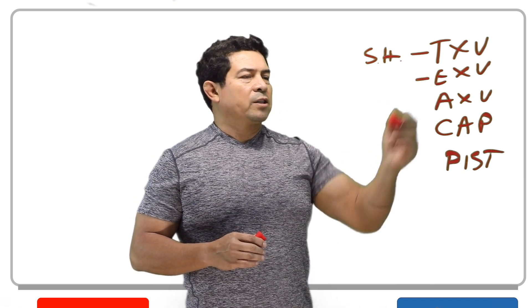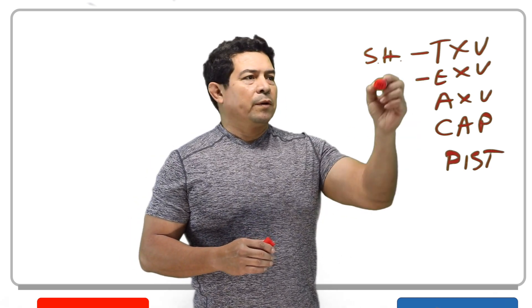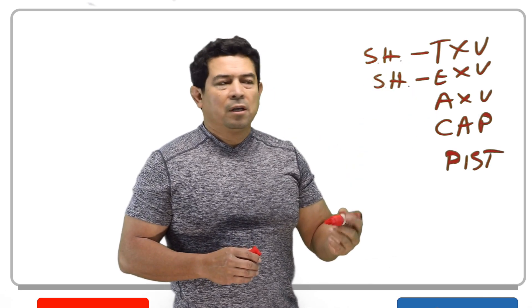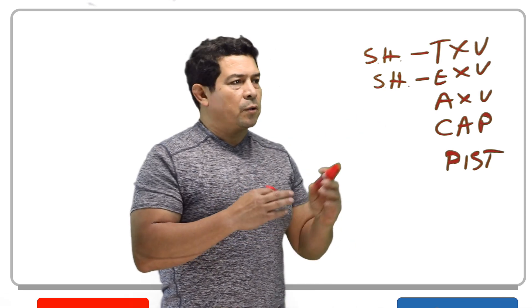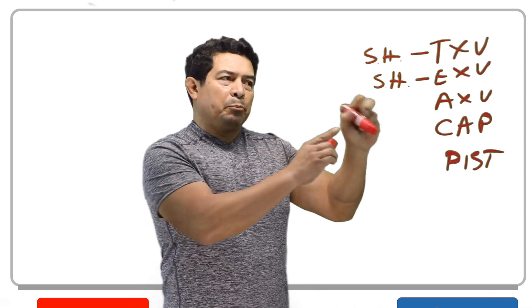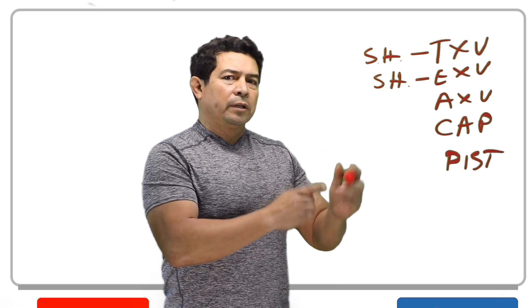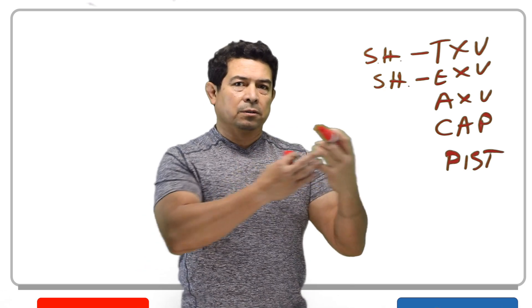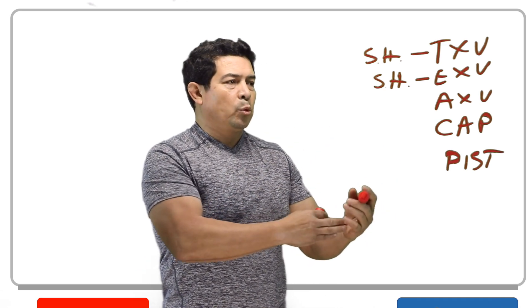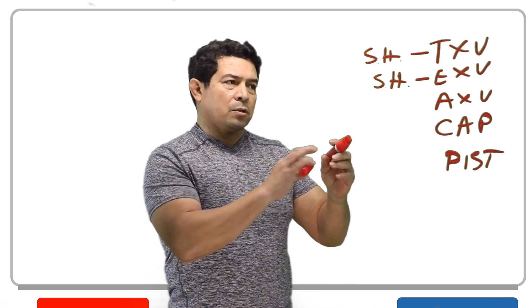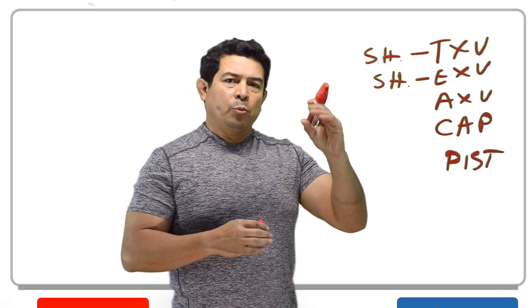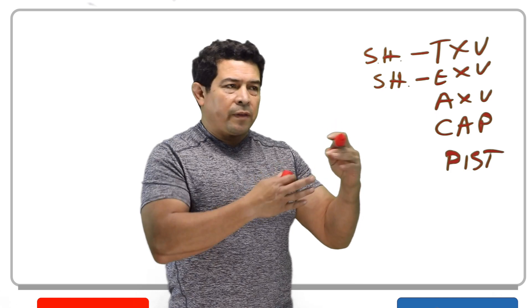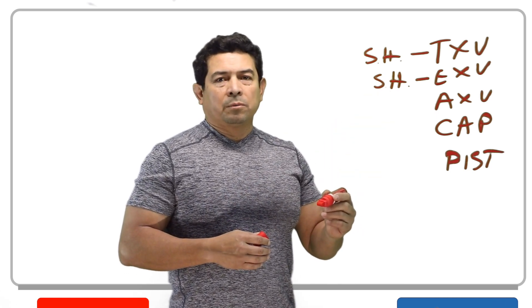The electronic expansion valve does basically the same thing — it maintains constant superheat, opening and closing and adjusting. But it does it all electronically. It has electrical sensors that send signals to a board, the board adjusts and sends a signal to the valve, and it opens and closes the valve electronically. It has a little motor in there — all of that to maintain constant superheat.